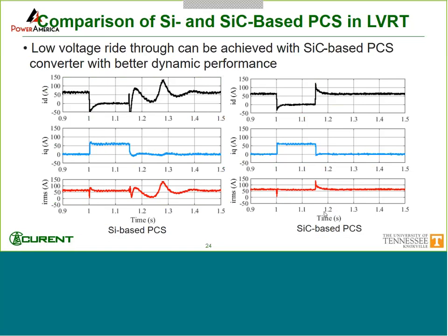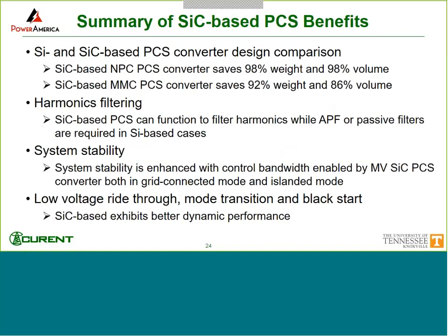So the low voltage ride through, I actually already showed this earlier, and this is silicon-based case and silicon carbide-based case, and they both can ride through on the grid side, but there is a little bit better dynamic performance. Of course, on the microgrid side, it's much better because the voltage can be maintained. So if I summarize the potential benefits of using silicon carbide-based PCS in an asynchronous microgrid, for the converter, huge savings in terms of weight and volume. And for the system level, it can provide harmonic filtering without adding much capacity. And it also can help with system stability and will have better low voltage ride through and mode transition capability.